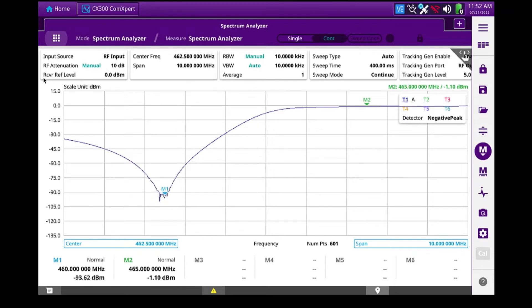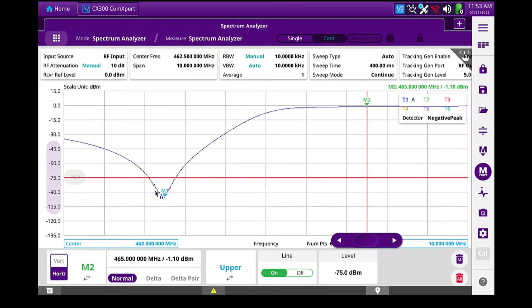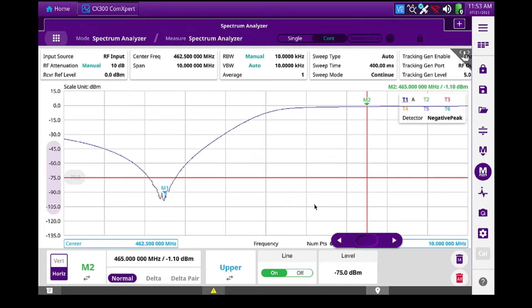So this duplexer has a minimum isolation specification of 75 dB. So I'm going to use a horizontal marker. And we'll go back to markers, change this to horizontal. We'll turn this on. And I'm going to set a minus 75 dB marker. So I will want any notches to be below this line. So I'm in good shape so far. So this duplexer has actually already been tuned.